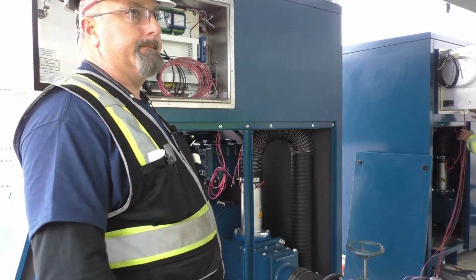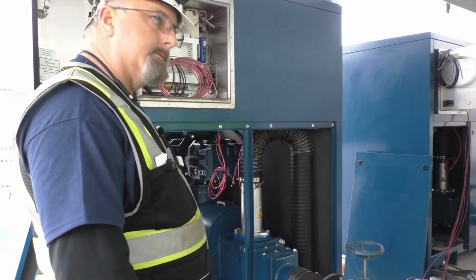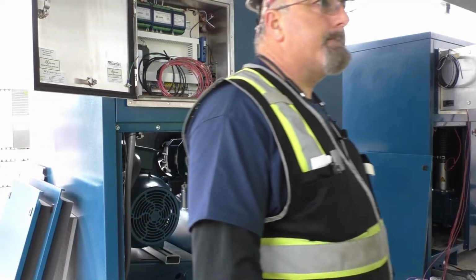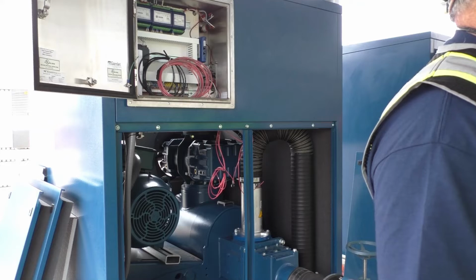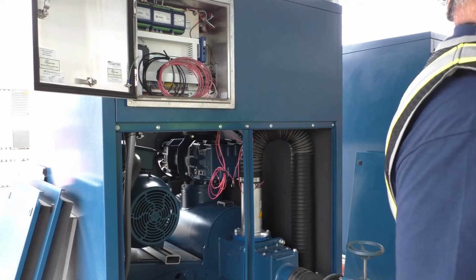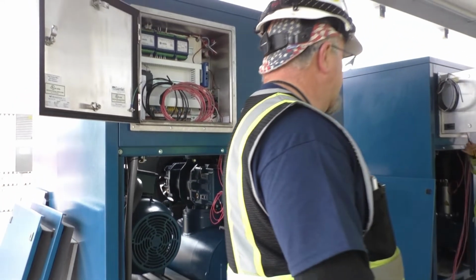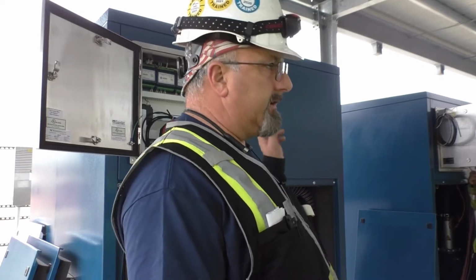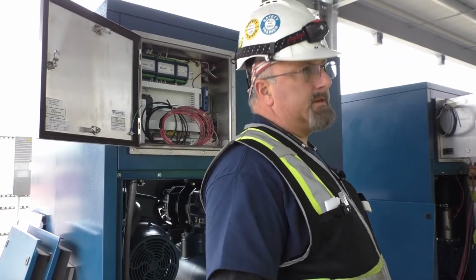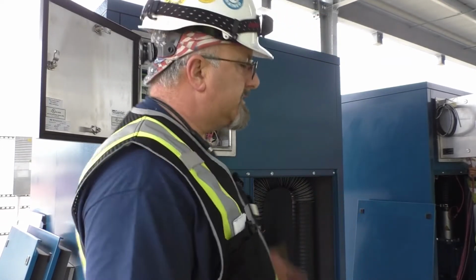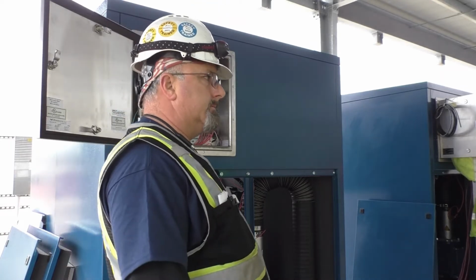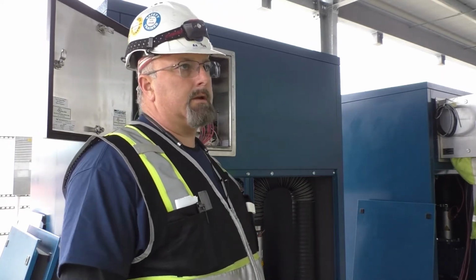One reason I asked is that someone had another piece of equipment and someone said, "Oh, this is run backwards." And, no, all 5 of these have been verified. They are running in the right direction. Initially, they were backwards. We changed it in the motor junction box. They're all turning the correct direction.